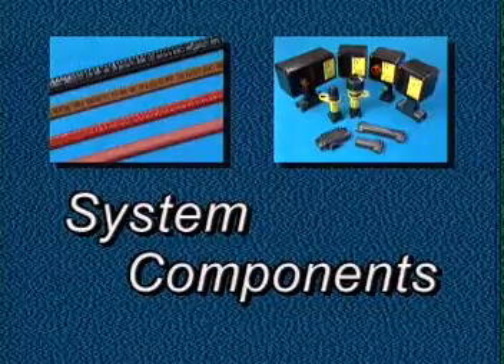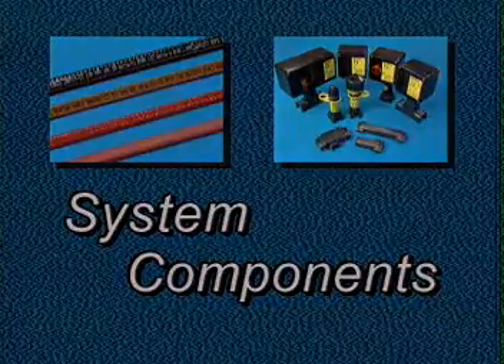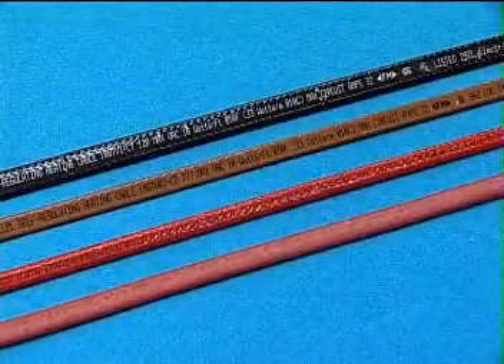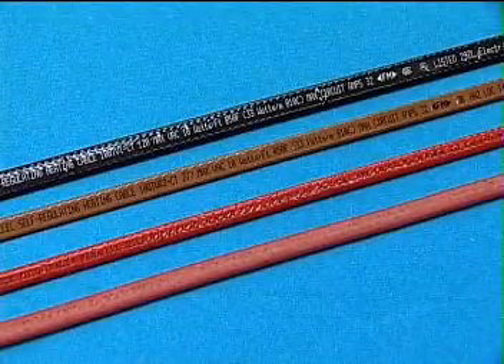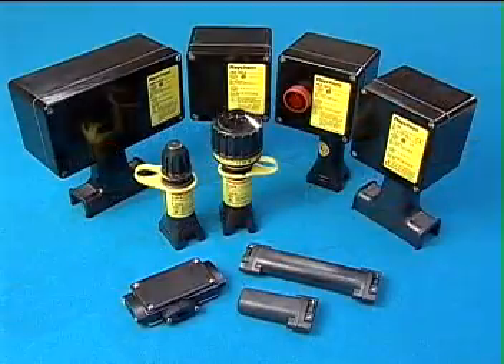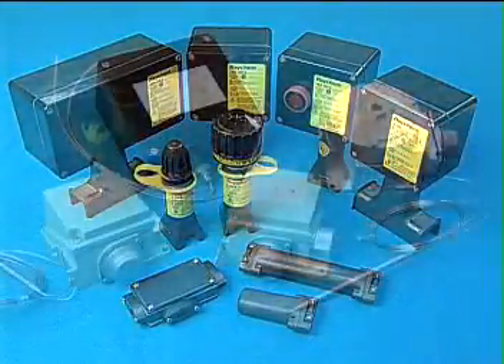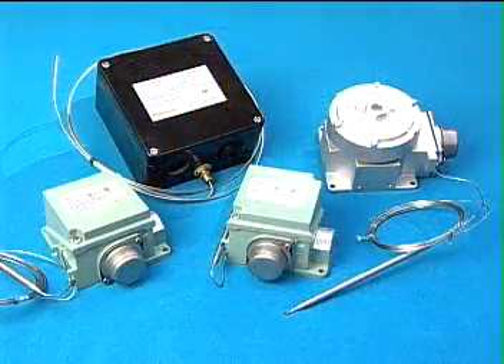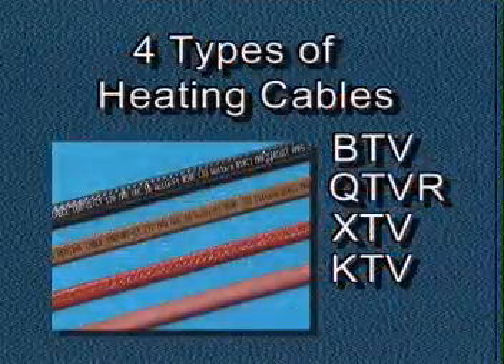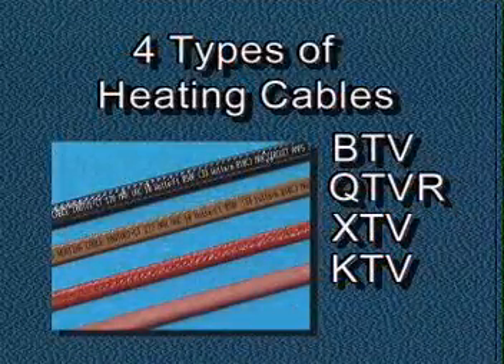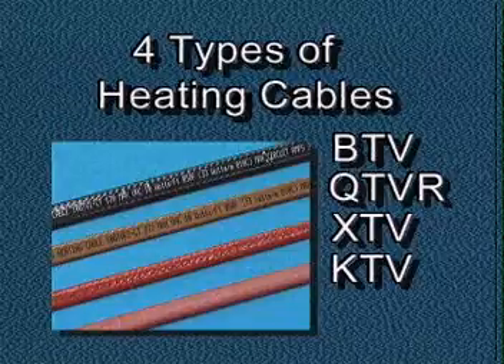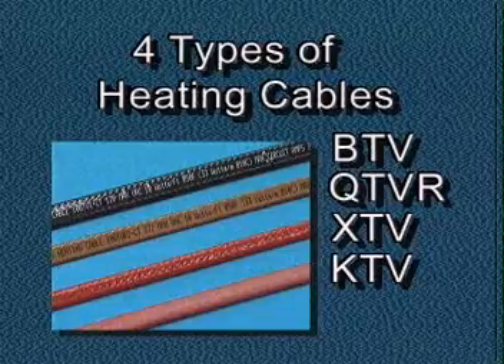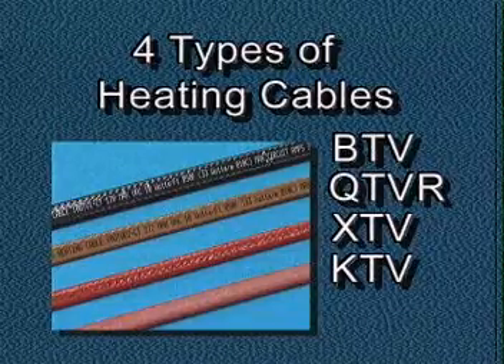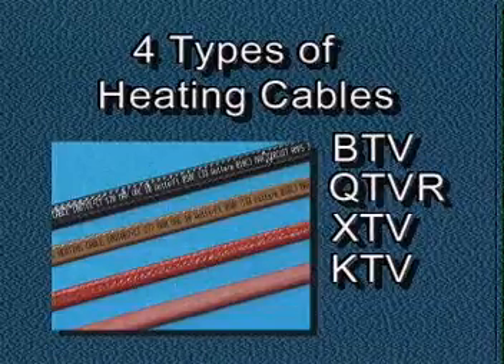First, let's look at the major components of the Raychem heat tracing system and see how they work. The system includes the heating cables, the connection kits, and the control devices. There are 4 types of heating cables that are installed on pipes for temperature maintenance and freeze protection. Each can be configured for use in ordinary or hazardous areas where there is possible exposure to corrosive materials.